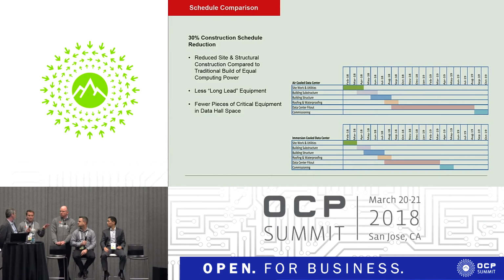NFPA doesn't currently recognize immersion cooling as a fire protection strategy, but potentially it is one. We can get rid of the fire protection systems too. That's also a byproduct of this we didn't get to, you bring that up - we can use a wet system over these tanks. This proposal we put together was pre-action on the whole thing, because we can get so outside the box here that you get the eye rolls. But you bring up the tanks and the fluids - the electrical equipment in here is rated at 30 AIC, and there's no arc flash for your guys doing maintenance because it's dielectric fluid. So it's a safe system to go in and work with the equipment there. There's no arc flash to it.